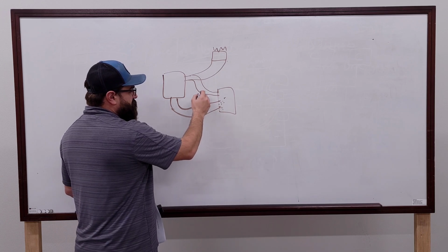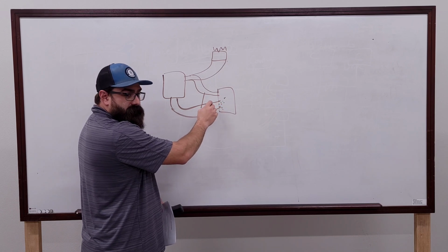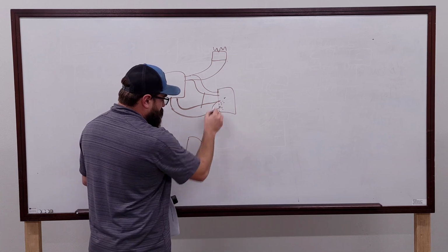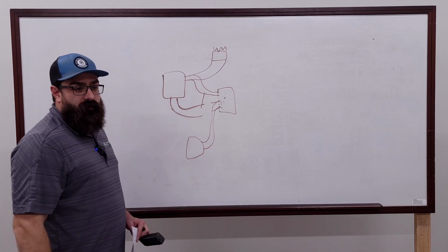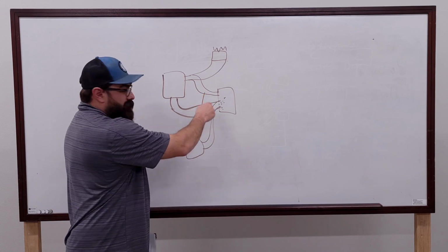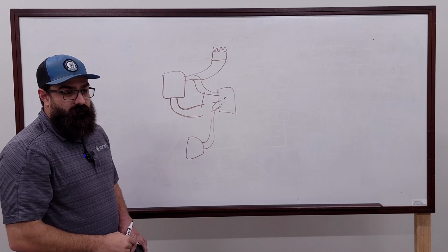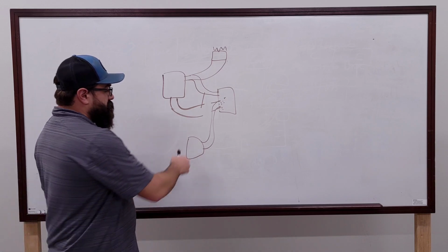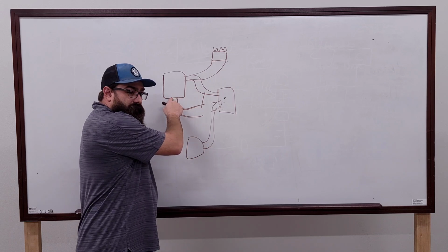Well, there may be something causing this common to get wigged out that's making you not get that 10 volts through these wires. But if you take a separate signal generator and wire up over here and take all this out, you've removed the short and it works. So, you know, your short's still back here, not at the physical device, it's somewhere else in the panel. And that may be what's causing your problem. So that's why I always like to take these off, make sure I have my signal there, make sure I have my signal at the controller.